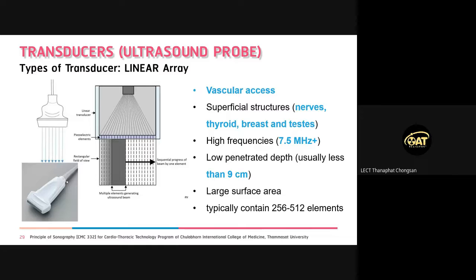For the PZT element of piezoelectric, one or multiple elements will be used for creating sound wave. For linear array, the PZT works in groups on this array, so it does not work at every PZT position at the same time.